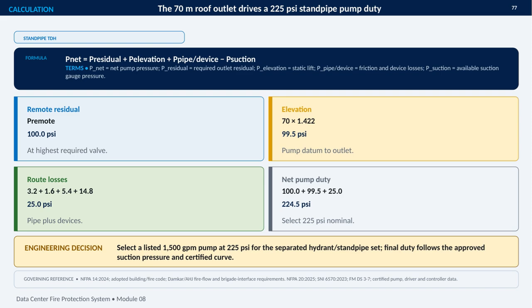Adding these requirements gives 224.5 psi: 100 psi for the remote residual, 99.5 psi for elevation, and 25 psi for friction and device losses. No suction pressure is subtracted in this displayed duty, so the selection is rounded to 225 psi nominal. The engineering decision is to select a listed 1,500 GPM pump at 225 psi for the separated hydrant and standpipe set. Final duty still depends on the approved suction pressure and the certified pump curve, with verification against the listed NFPA, SNI, FM, code, and AHJ requirements.